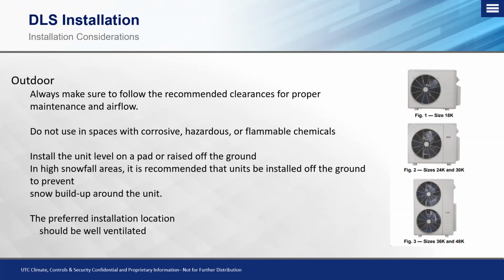If we don't, snow will build up on the side of the coils, block the amount of airflow that can get to the unit, and of course we know it will not properly defrost, and it will also reduce heating capacity. So the units do need to be lifted if they are going to be in an area that experiences not only cold conditions, but more importantly, high snowfall where it could build up around the condensing coil. And of course, the preferred installation location is going to be somewhere that's well ventilated. We don't want to stick this inside or in an area that's not well ventilated, where we can get good air coming across the coil as we are in different heating and cooling modes.